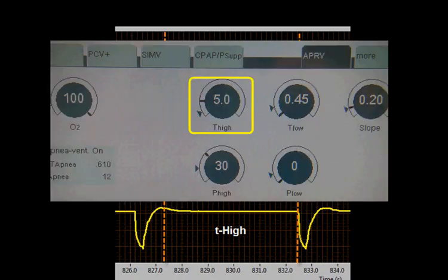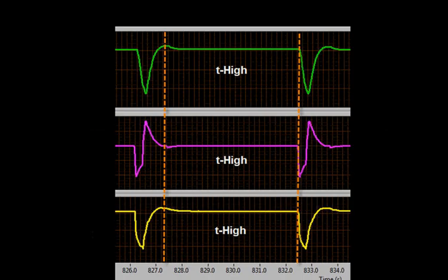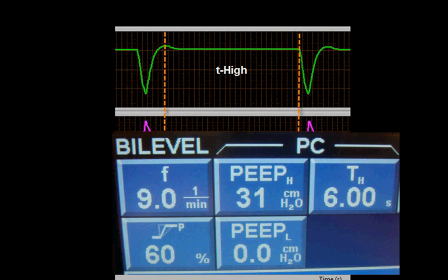The setting name T-High is used to describe the settings on the Draeger, Hamilton, and Maquet ventilators. However, in bi-level mode, the Puritan Bennett 840 uses T-H for the high PEEP time when naming T-High. Additionally, you can set a frequency; however, this can affect optimizing maximum recruitment and release times.